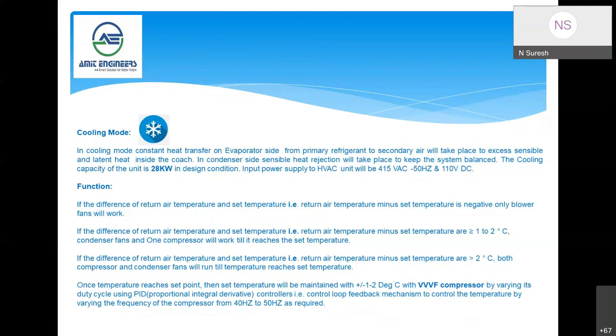Basically, if the return air temperature minus the set temperature is negative, only the blower fan will work. I'm going through the function of the system, how it works. Similarly, if the difference is greater than or equal to 1 or 2 degrees Celsius, the condenser fan and compressor will work till it reaches the set temperature. And if the temperature is more than 2 degrees, both compressor and condenser fan will run till the temperature reaches the set temperature. Here is how the VVVF compressor is working.